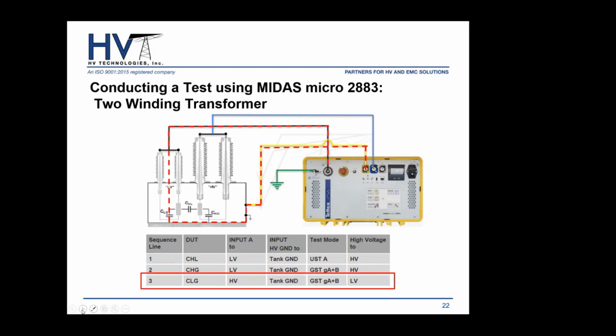And once we do our low voltage, we'll switch our high voltage cable, put that on the low voltage, and the measuring will go on the high. Again, we'll use grounded specimen test, guarding A and B, because we do not want to have any other capacitances included in our measurement, and you hit start.